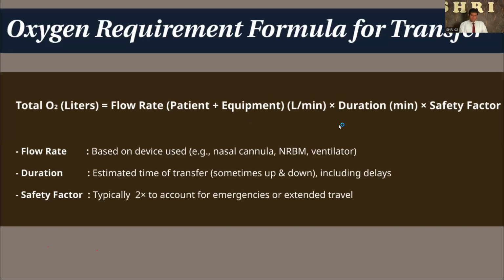And then the duration of the transfer in minutes, as I mentioned previously, is not the travel time only, but the total time of patient dispatching. And we always have a safety factor. The safety factor is 2 times. If my patient takes 40% oxygen, that means 10 liters per minute via the red color venturi device, and that is the current level.